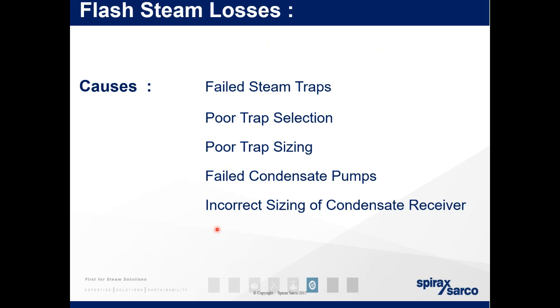That's for cold startup. As you start your steam system and you're warming up, you will produce more condensate than at any other time. So we recommend that you double the size of the trap from the load, as we said, so 2 times load, to size the trap correctly.